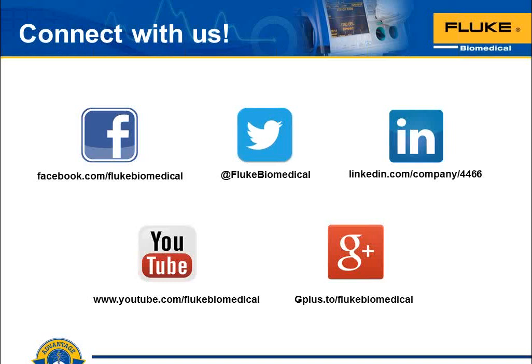In the meantime, the first question that came in, Jerry, is can Fluke's QA-ES test force triads and force FXs? Indeed, it can. Valleylab prefers that you do not use QA-ES2 for calibration adjustment. However, for performance testing, there is no reason why you cannot. Everything will work. You'll get your measurement values, and it all works well.